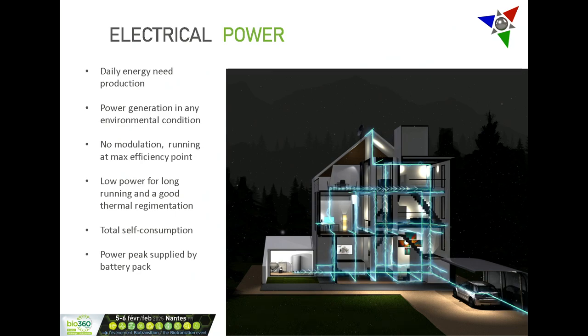So the micro-CHP for domestic application should be sized on the energy need of the house and not on the power peak need. There is no modulation. This system should always work at the best efficiency point.